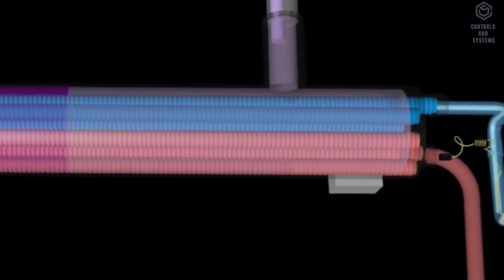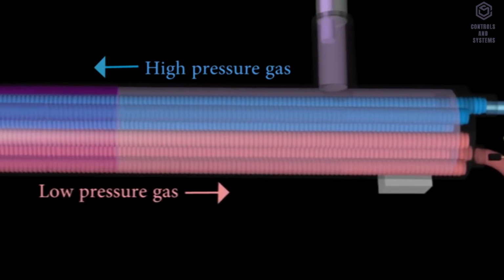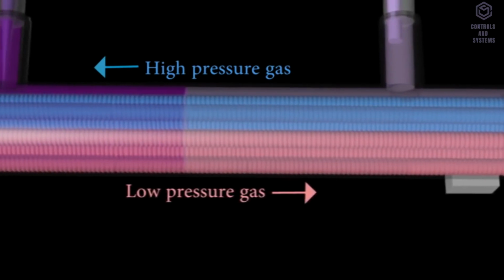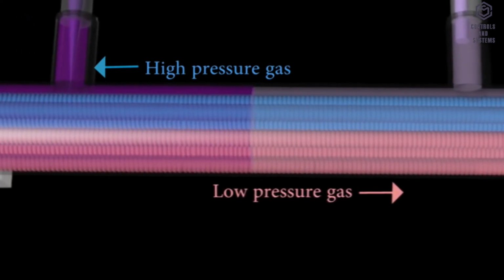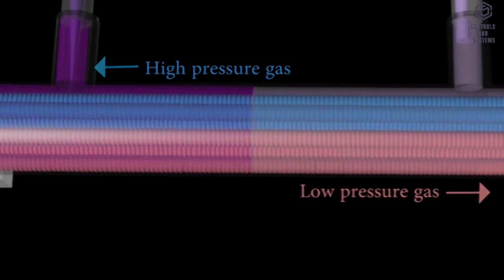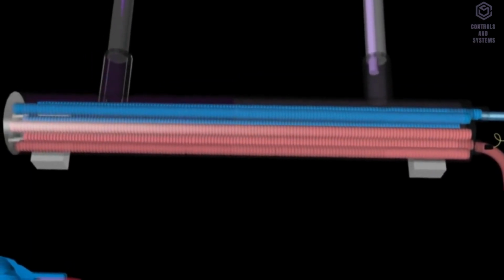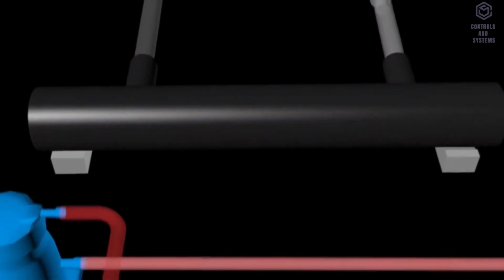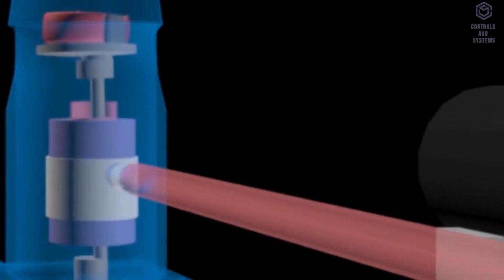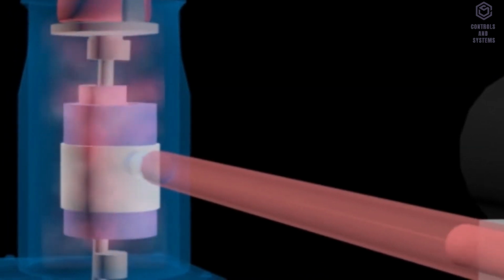The evaporator most commonly used is the shell and tube type, where the refrigerant flows in the tube and the water flows in the shell. The evaporator is insulated within the installation to reduce heat transfer. The refrigerant as low pressure gas will return to the compressor and continue to the next cycle.